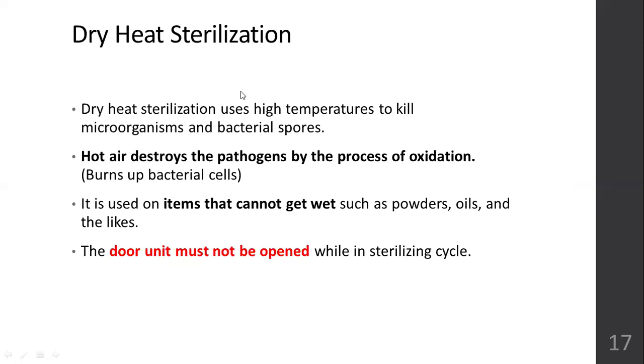Dry heat sterilization. It uses high temperature to kill microorganisms and bacterial spores. And hot air usually destroys the pathogens by the process of oxidation. It burns up all the bacterial cells. And it is used on items that cannot get wet, such as powders, oils, and all.